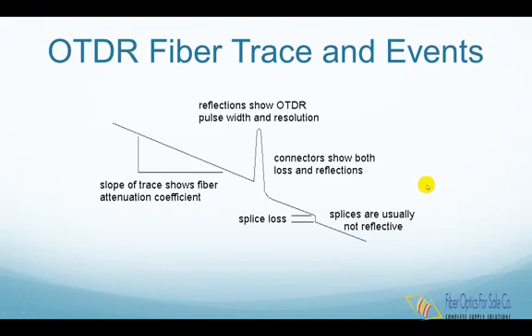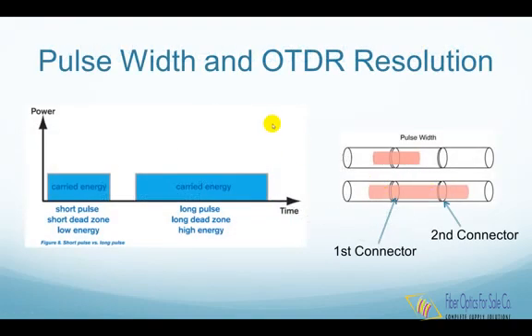Reflective pulses can show you the resolution of the OTDR. You cannot see two events closer than is allowed by the pulse width. Generally, longer pulse widths are used to be able to see farther along the cable plant, and narrower pulses are used when high resolution is needed, although this limits the distance that the OTDR can see.